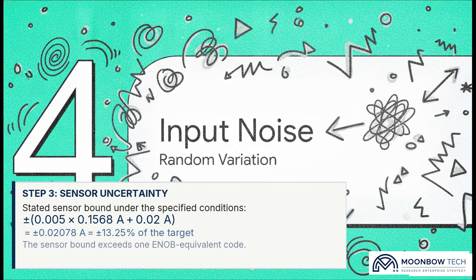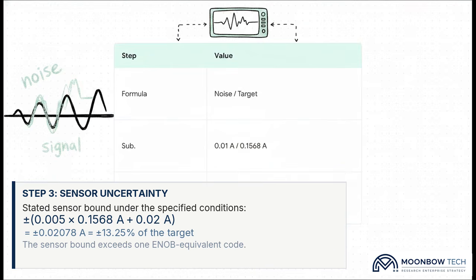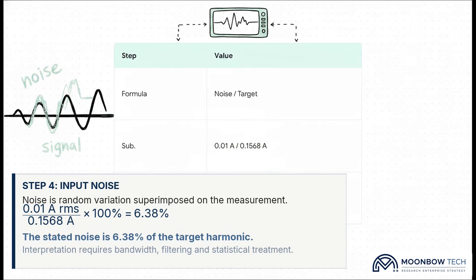Step 4. Input noise. The real world is messy, and random external variation is constantly superimposing itself onto our measurements. Let's say our instrument has an input noise specification of 0.01 amps root mean square. Let's see how much of our signal that noise obscures. Input noise divided by target harmonic. We substitute 0.01 amps divided by 0.1568 amps. The result is 6.38% of the target harmonic.